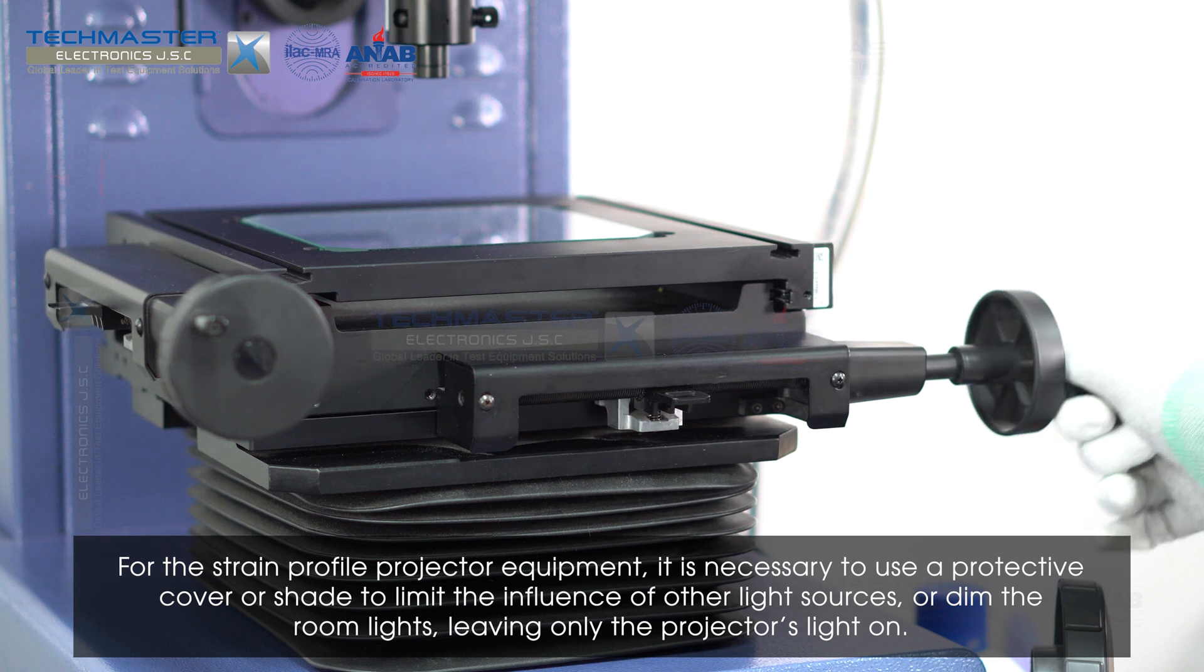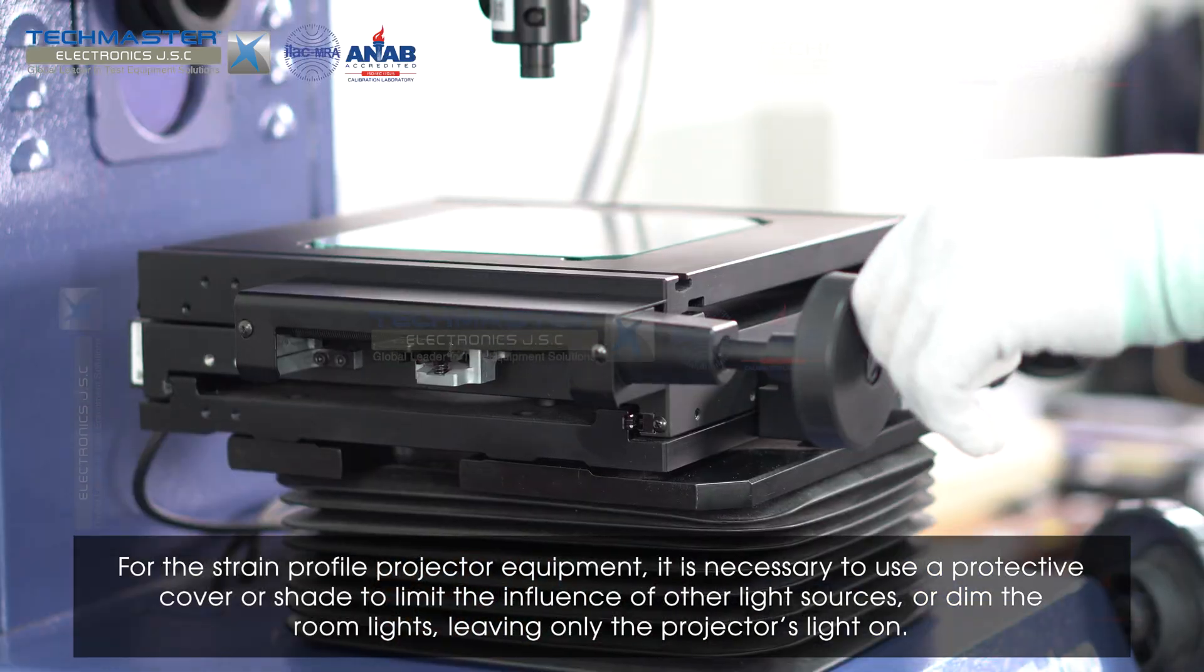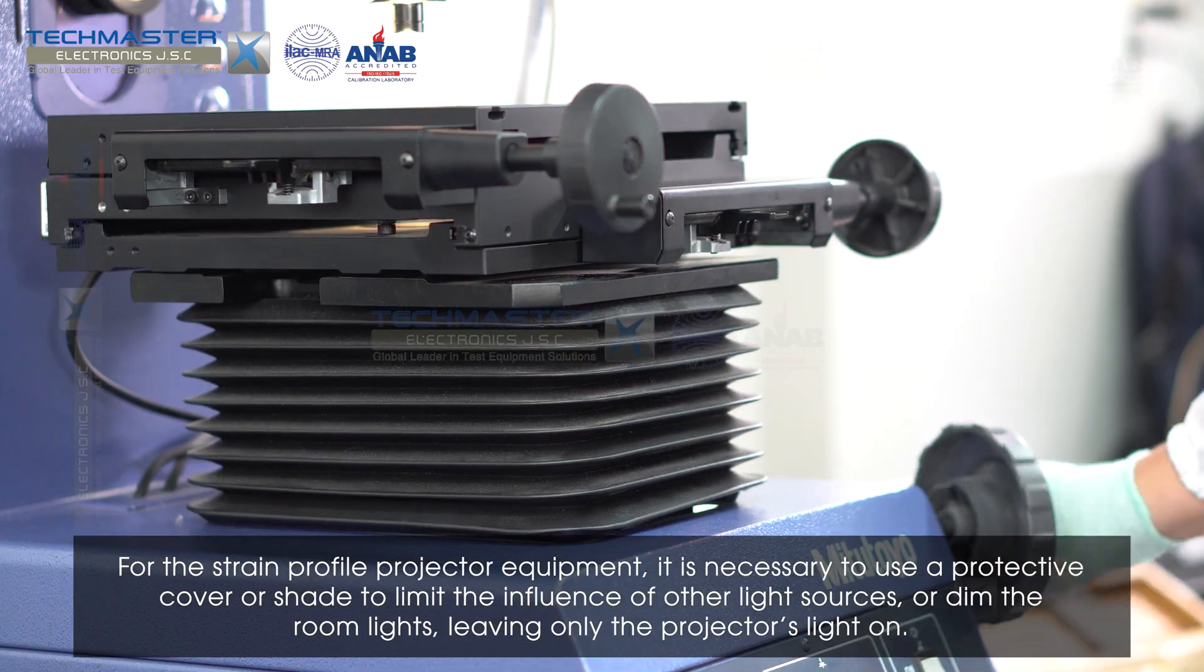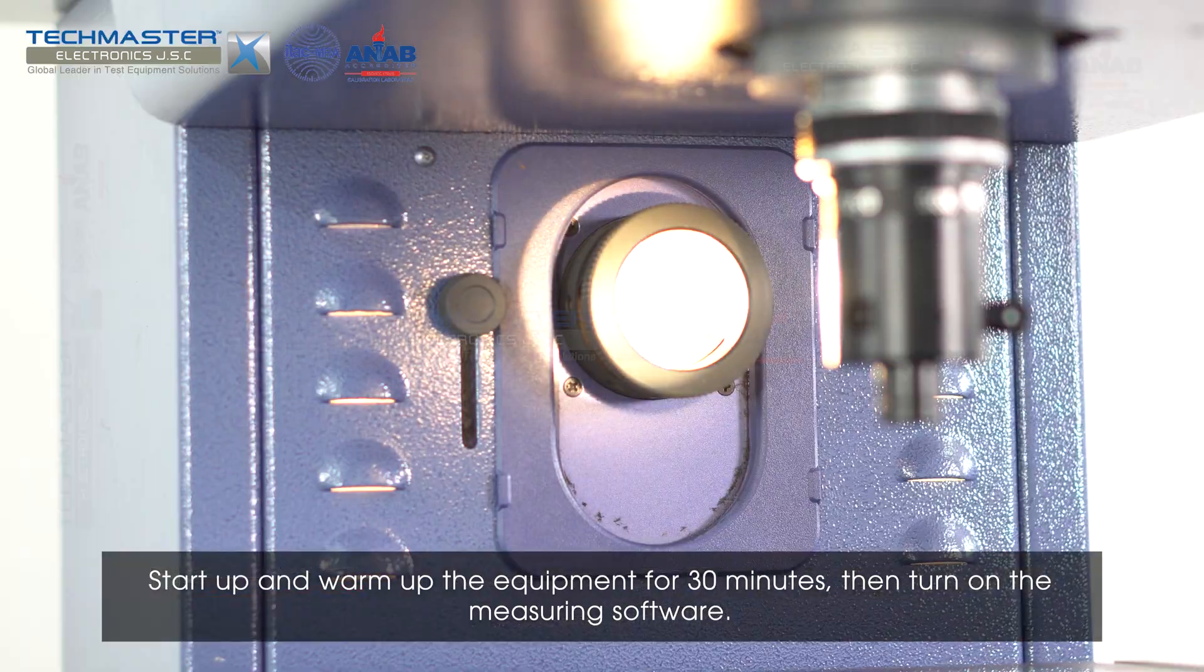For the strain profile projector equipment, it is necessary to use a protective cover or shade to limit the influence of other light sources, or dim the room lights, leaving only the projector's light on. Start up and warm up the equipment for 30 minutes, then turn on the measuring software.